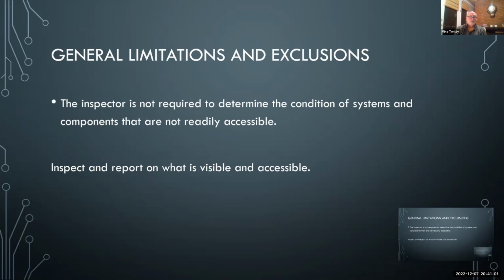So what you should do is inspect and report on what is visible and what is accessible. Put that in your report. I typically had a blanket statement in mind that generally around here on existing homes, of course, a lot of them older, the ground rod has gotten subsurface. You can't see it. You see a grounding conductor going down into the earth. I would have a blanket statement that the grounding electrode conductor was observed, it was inspected, it was proper size, and the ground rod was not visible. Or if it was, only the top of the ground rod and the connection was visible. I didn't make a statement that the home was properly grounded in all cases.